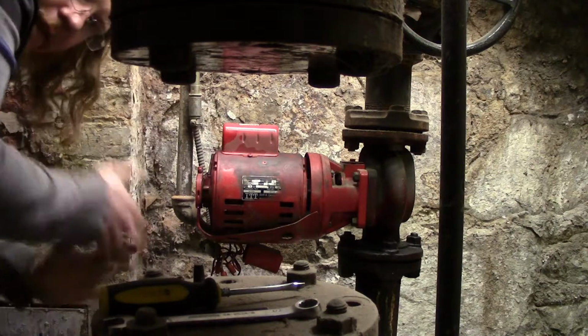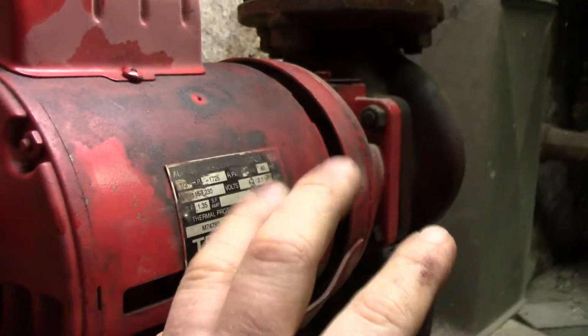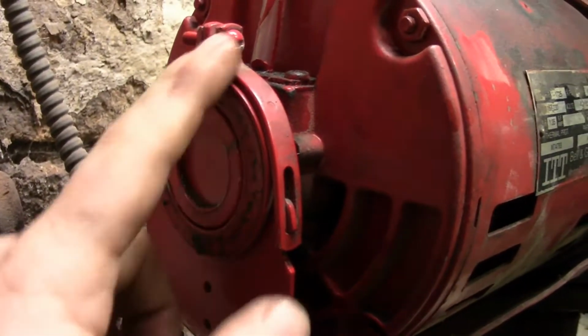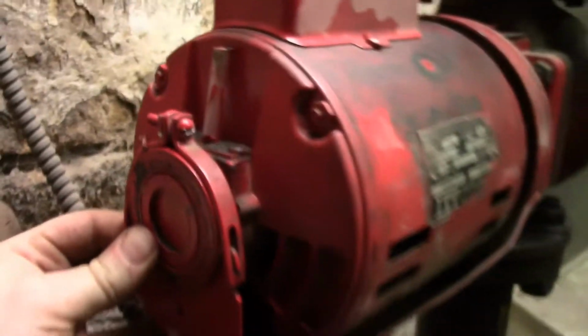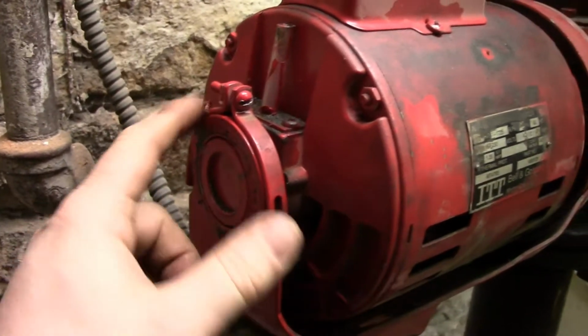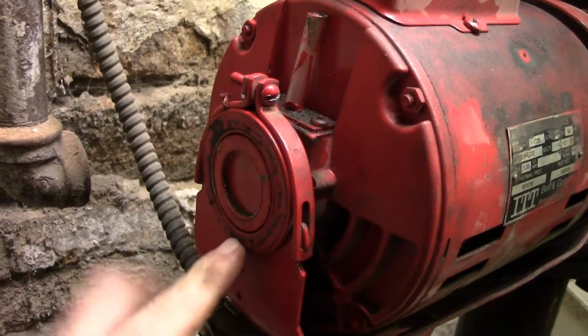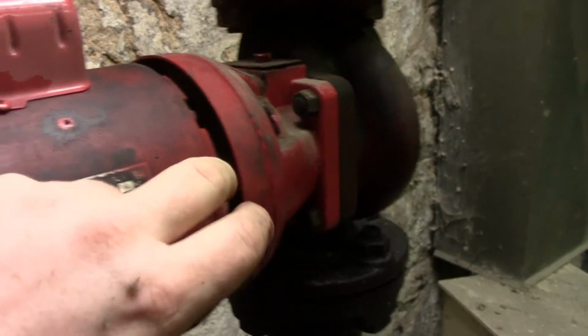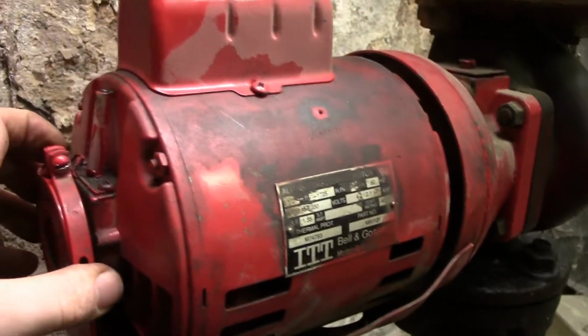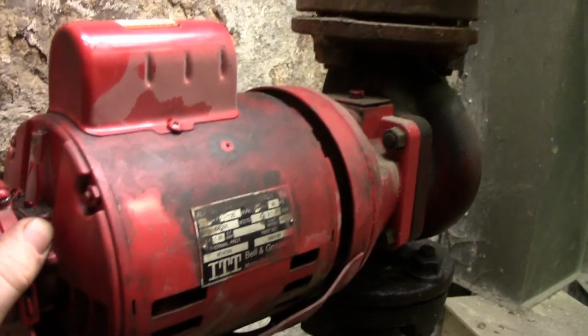Now, one thing you're checking when you blow your couplings up is whether or not your rubber mounts have sagged. The motor itself flexes a bit on these rubber mounts. And over time it'll actually sag on the rubber, and you'll end up seeing less rubber down here, more rubber up here. This causes a misalignment in the coupler, and that's what causes it to wear out to the point of blowing apart. This one here was fine, but if I didn't check for that, more than likely I'd put the new coupler in and in a couple of months it'd blow apart again anyways.